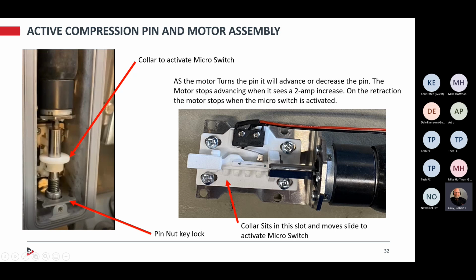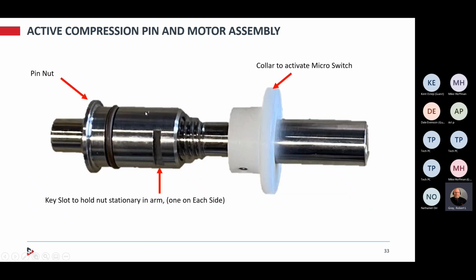We don't want this collar coming back and hitting this member right here, breaking it, or we don't want the pin to come all the way back and overamp the motor on the retraction. So what it's doing, it's looking for your deactivation of your micro switch or switches now, because now version 2, again, there's your pin again. This is the pin that comes out. You're just going to turn your nut to get the 3/16 or 16th of an inch sticking out the back.